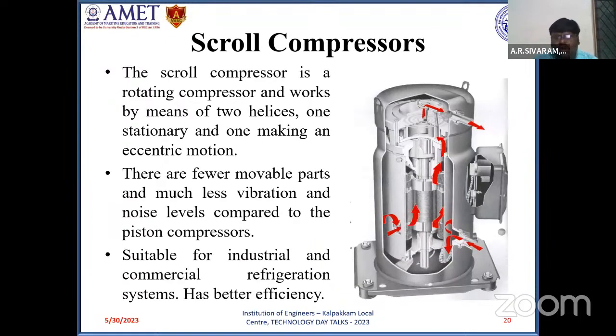Coming to the next type, the scroll type of compressor. Out of all the 5 types of compressors, this has the best efficiency, and it has 2 helices. One helix is fixed, and the other is movable. The fixed helix is fixed, and the movable helix is connected to the motor present in the compressor through a shaft. The movable helix undergoes rotary motion, and refrigerant gets compressed between the movable helix and the fixed helix, and it leaves at high discharge pressure.